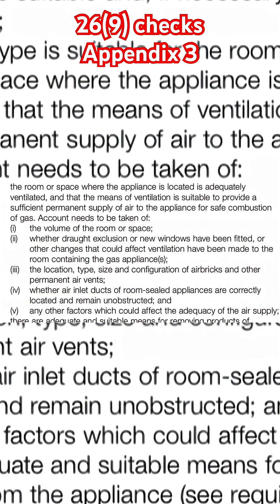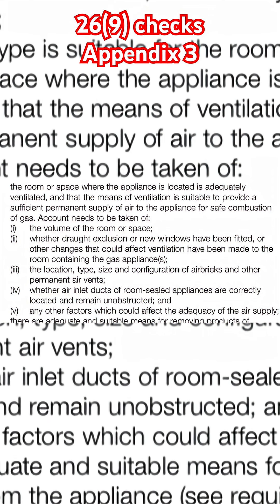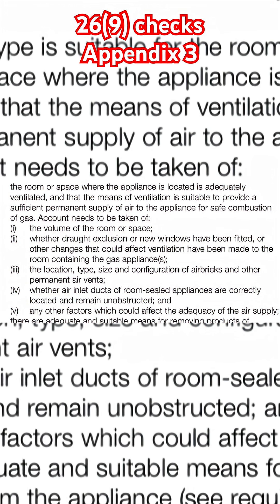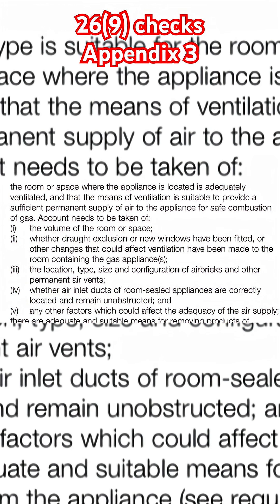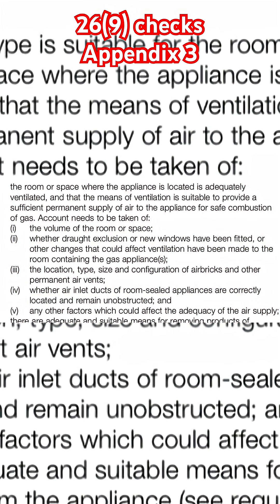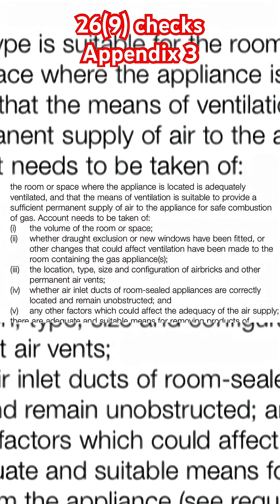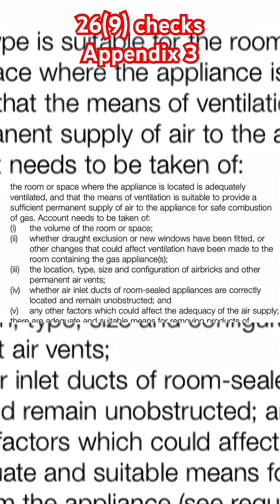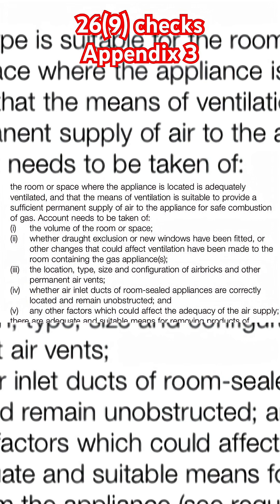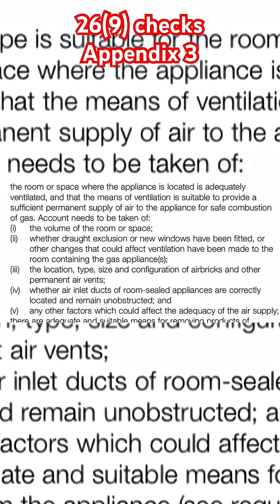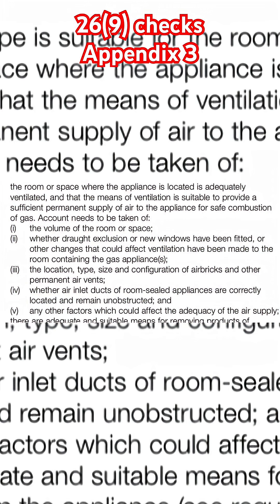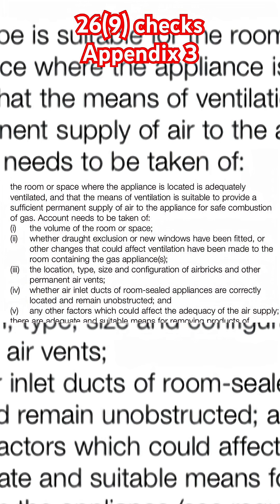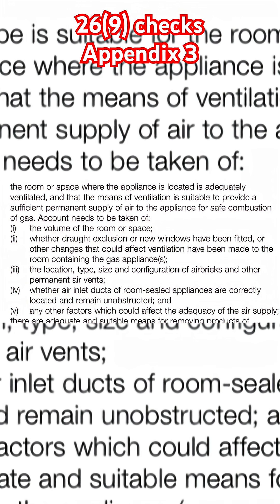Account needs to be taken of: C1, the volume of the room or space; C2, where draft exclusion or new windows have been fitted, or other changes that could affect ventilation have been made to the room containing the gas appliance or appliances; and C3, the location, type, size and configuration of air bricks and other permanent air vents.